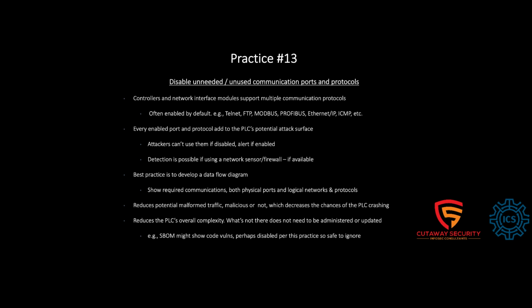The other advantages following this practice is it reduces the potential for malformed traffic to impact the PLC, cause it to crash, because that section, that protocol, that port is disabled. And then also reduces the overall complexity, because what's not there, what's not being used, doesn't need to be administered or updated. We hear a lot about software bill of materials.